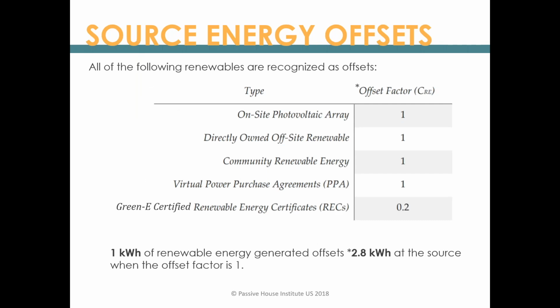So the sentence at the bottom here: 1 kilowatt hour of renewable energy generated offsets 2.8 at the source when the offset factor is 1. The source energy factor for electricity in the US right now is 2.8. So if you generate 1 on site, we say you offset 2.8 at the source. Essentially, if you're an all-electric building, you reach site net zero the same time you reach source net zero—you're not generating 3 times more than you need on site, it's the same offset, you're either offsetting 1 at the site or 2.8 at the source.